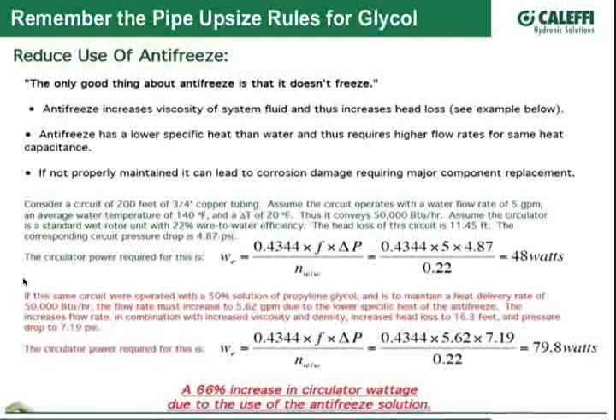You might be able to get away with the pump that's already in there. If it's a multi-speed pump, you might bump the speed up, but there comes a point where you might have to increase the pump size to move that amount of heat. That's not going to cause it to freeze, it just means if the pump was undersized, you're not going to be able to move that many BTUs through the piping. So just know there's a multiplier and tables available to come up with that correction.